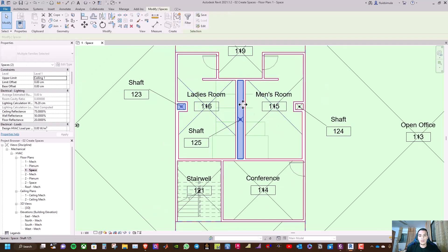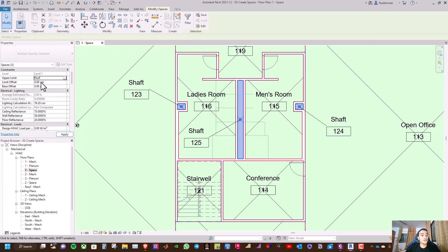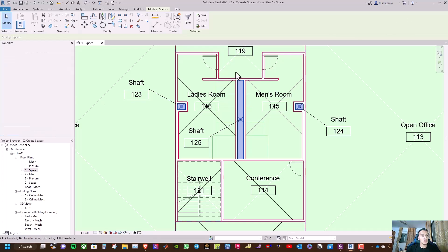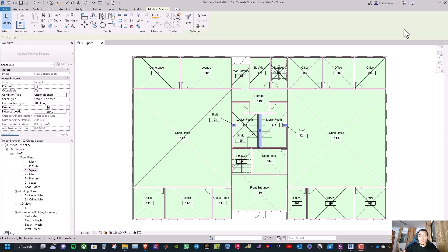We need to select these three shaft spaces and modify their height. At upper limit, change it to roof, and set the limit offset to minus 21 cm. Under energy analysis, select unoccupied — so untick that option — and also change the condition type to unconditioned. When Revit calculates heating and cooling loads, it will not count unconditioned and unoccupied spaces.